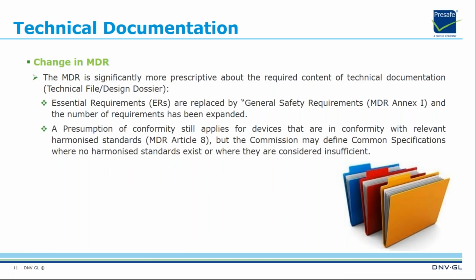The other change is relevant to technical documentation. Some new requirements are relevant to this technical documentation. The MDR is significantly more prescriptive about the required content of technical documentation, including the technical file and design dossier. Essential requirements are replaced by general safety and performance requirements based on Annex 1 in the MDR, and the number of requirements has been expanded. The presumption of conformity still applies for devices that are in conformity with relevant harmonized standards based on Article 8, but the Commission may define common specifications where no harmonized standards exist or where they are considered insufficient.